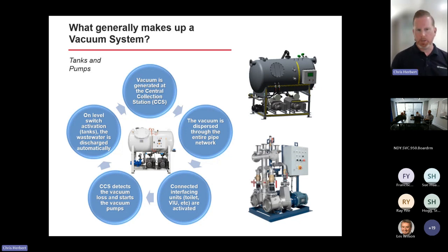Thankfully, with the tank style system, we do have some residual vacuum. So even if the pumps don't kick in, we might get 3, 4, or 5 flushes before the system is completely void of any vacuum to transfer any more waste.